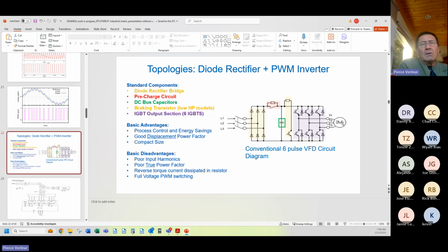If they just say one thing, oh, the voltage drop across the matrix drive is 10% and it's going to undervoltage the motor, but they don't tell you that we've been doing the same thing with variable frequency drives since 1983. And because NEMA says the motor can run at 90% of its rated voltage and still achieve output torque with the correct thermal losses, because that's what the motor is designed for. So that is the counter to the big claim against matrix drive.